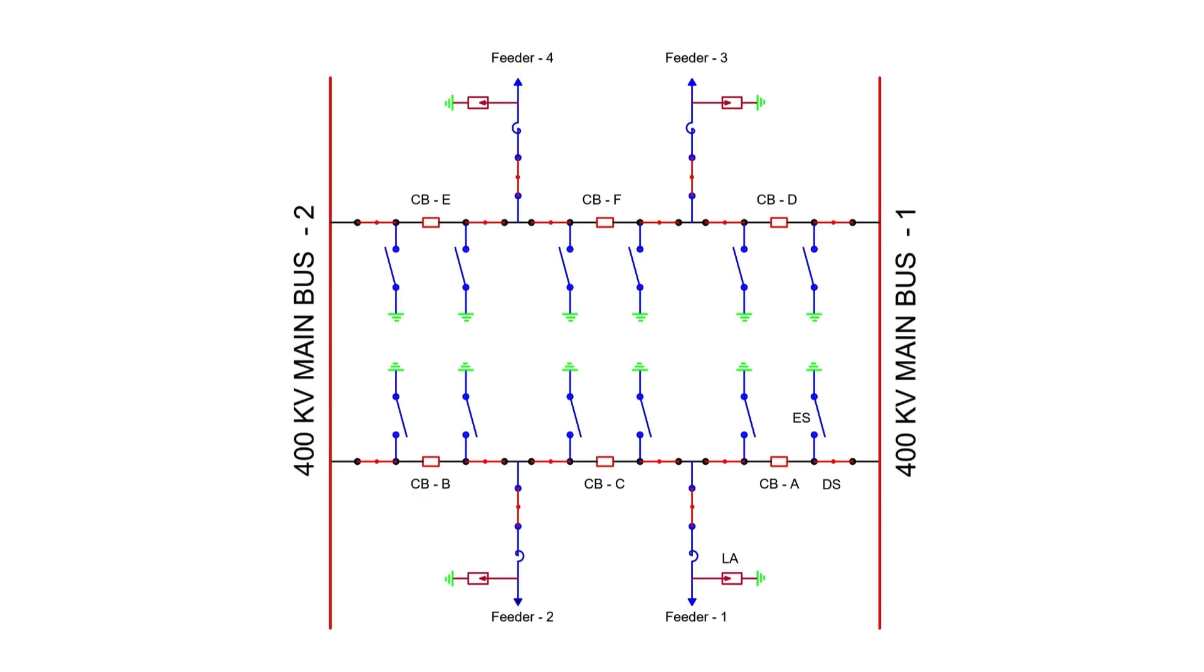For maintenance, if we need to work on circuit breaker B of diameter one, we can open circuit breaker B, isolate it by opening these two isolators and close this earth switch. Notice that neither feeder one nor feeder two will go out of service. Feeder two will still be fed through circuit breaker A and circuit breaker C.